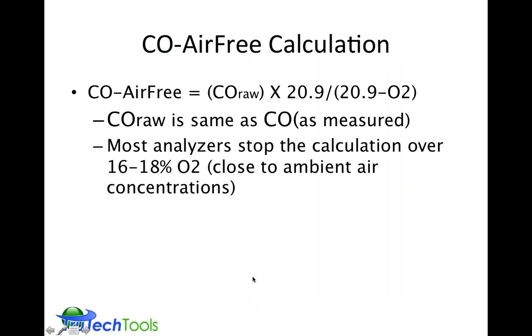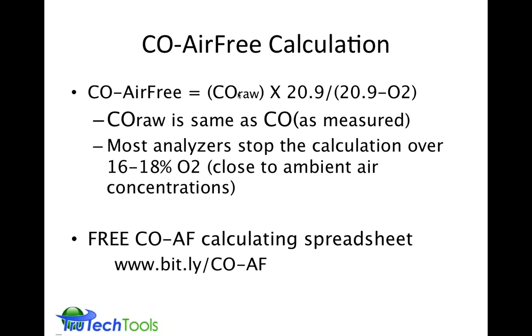So the calculation here, you don't really need to know it. Sometimes it's interesting for people to know it, but it uses the CO raw level and the oxygen level from the sensor. The CO raw level is also sometimes called CO as measured. It's the diluted value that you're measuring wherever, in the ambient, in the stack, etc. And most analyzers stop doing this calculation here when oxygen gets above 16 to 18% oxygen, because the numbers kind of blow up. They get very, very large. So the CO air-free test is usually done in the stack, and it's a calculation using oxygen and CO.